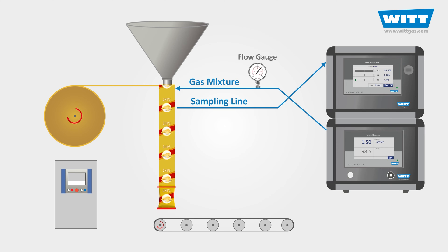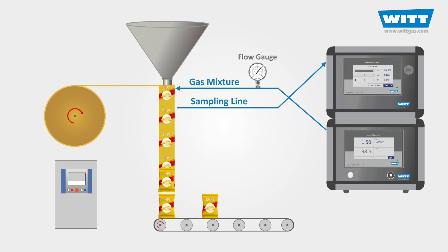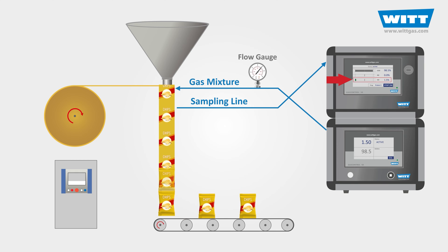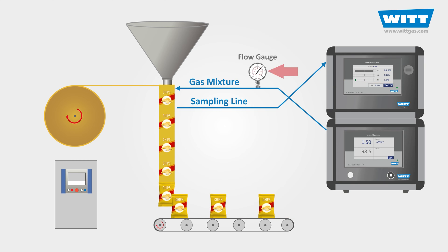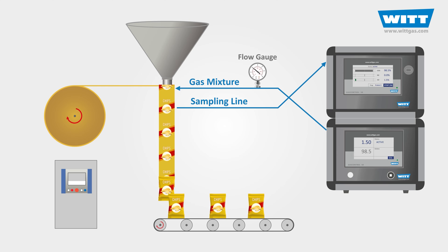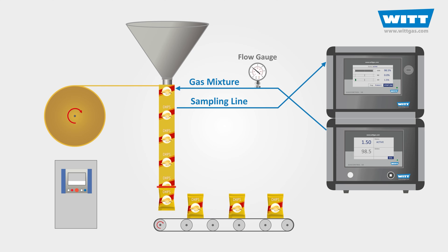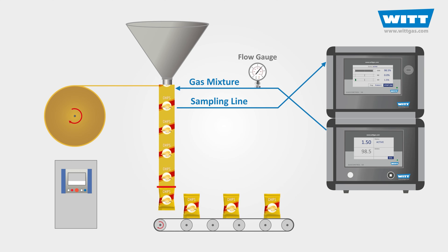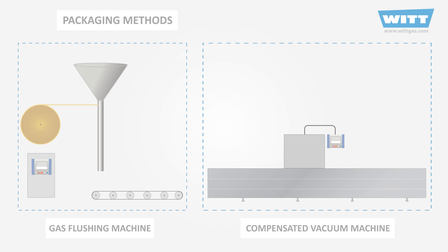By means of a lance, a sample is taken continuously from the pillow bag and analyzed. As long as the oxygen value is below the set limit value, the amount of supplied protective gas is reduced. If the oxygen content approaches the limit value, the protective gas quantity is automatically increased.